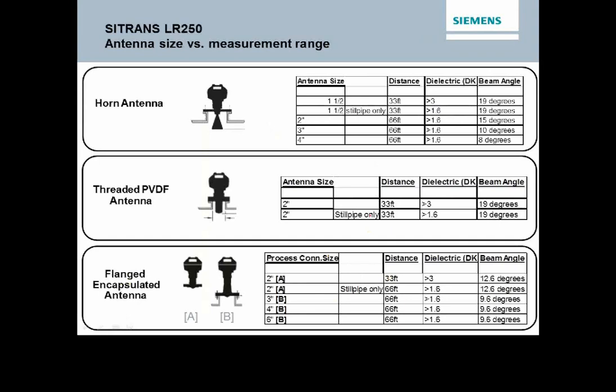With the LR250, we're looking at 66 feet and 33 feet. And you can see that as we get into the larger sizes, we get smaller beam angles as well. An important note here is that the dielectric constant of the material matters: materials with lower dielectric constants don't send as strong a signal back, so they're a little bit harder to measure. But we can measure dielectrics down as long as they're greater than 1.6. Most of these dielectric constants have been taken from actual physical measurements. A number of universities in the past studied dielectric constants, so a reference material is readily available.